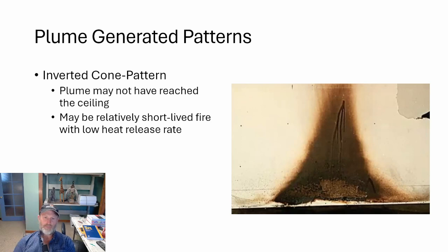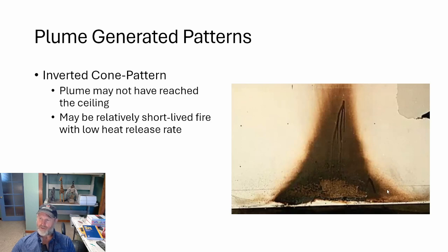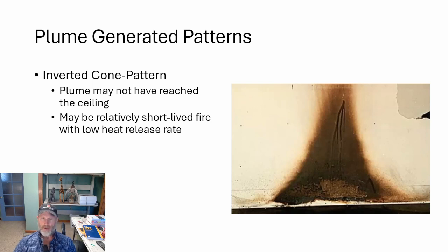So a 22-degree pattern is what you'll normally see in larger fires, unless there are obstructions or buoyancy effects. But if you have a small fire, the width is defined by the base of fuel involved, and it's just not a very hot fire — it quickly peters out. It doesn't create a plume jet that reaches the ceiling to create a ceiling jet. It's fairly short-lived with a very low heat release rate.